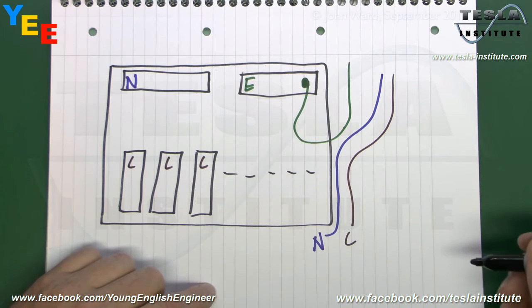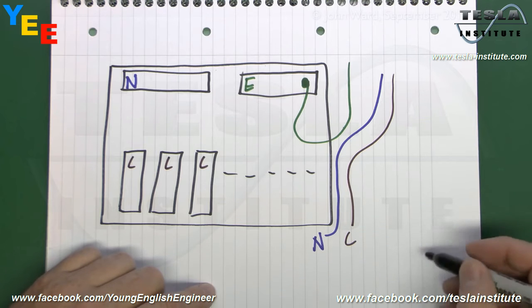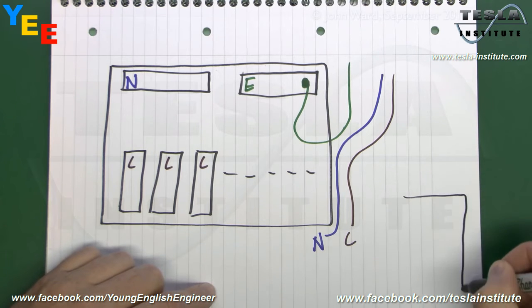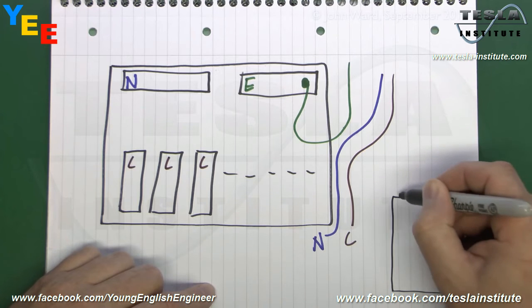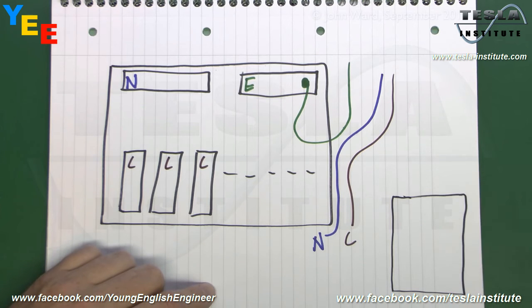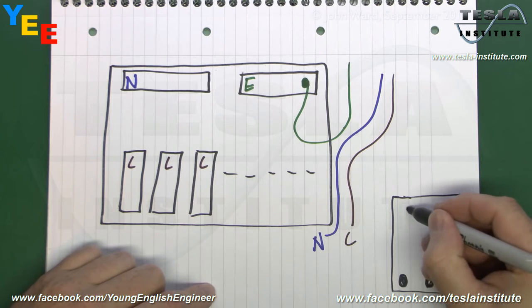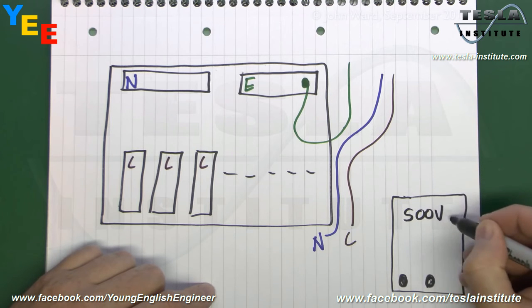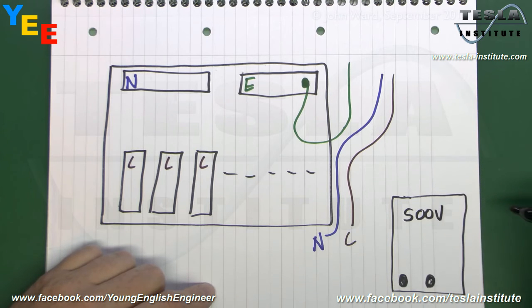Now in terms of the test equipment, it's quite a straightforward thing. You can get separate testing equipment which just has the single function built in, or more usually these days you would have a multi-function tester, so it's just a question of selecting the appropriate setting on the front. But you'll have 2 leads coming out of the device, so 2 terminals there, and it's a question of connecting one to each of the things you're going to be testing. And as we saw in the table previously, you do need to select the correct test voltage, which would typically be 500 volts on the device itself.